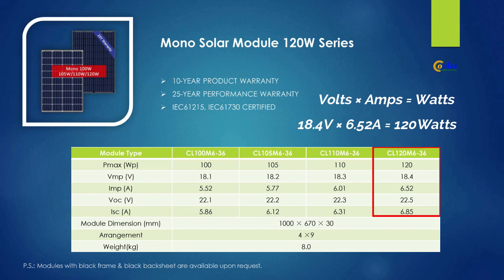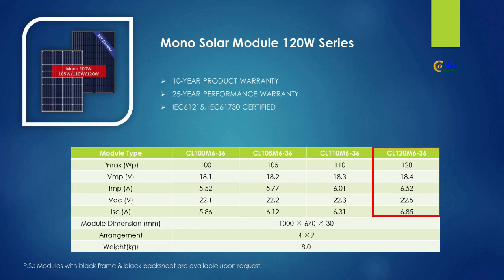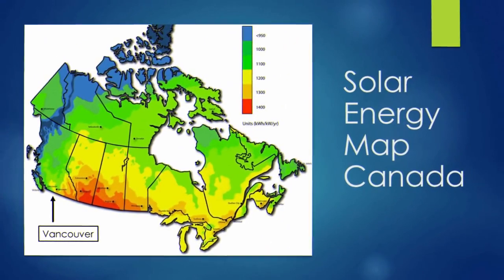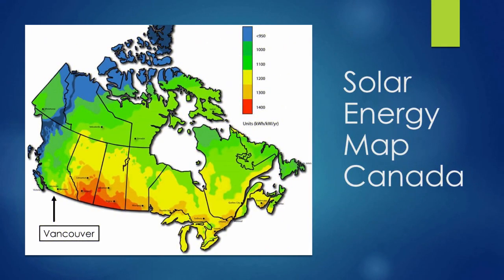The rating of the solar panel is based on one hour at standard test conditions. Obviously during the day we're going to have a varying amount of sunshine — in the morning between 8 and 9 o'clock the sun's irradiance is about half of what it would be at midday. So we need to look at historical data for our area to find out how many average daily peak sun hours we can expect.